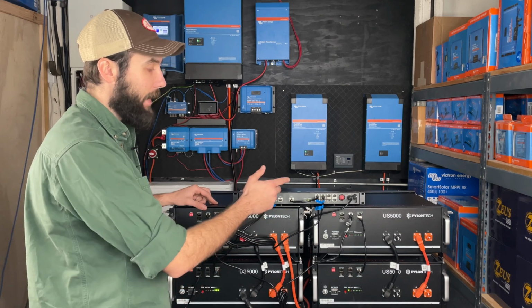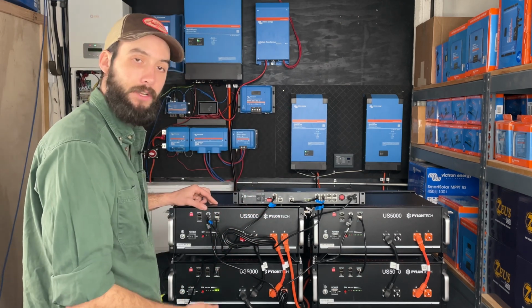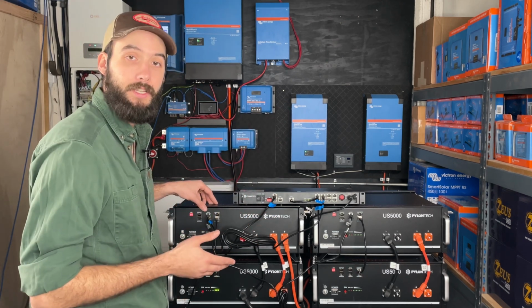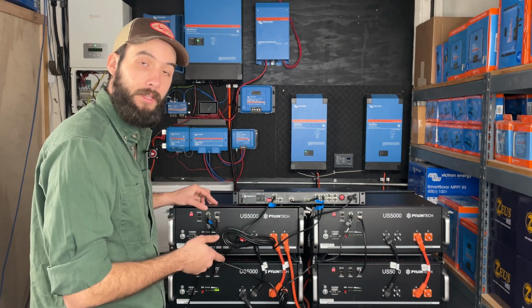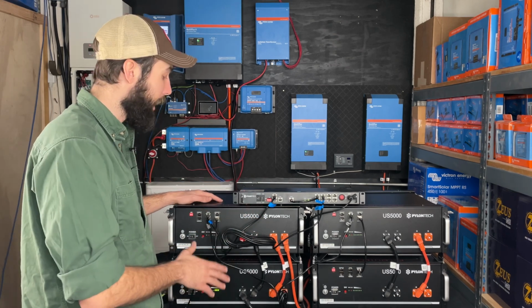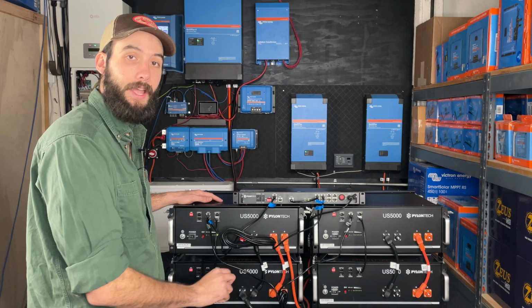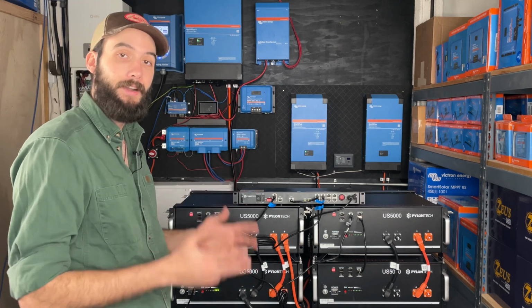So if we had a stack of 16 batteries, and for some reason, because it's an oversized system, I only had one set of end runs, that's fine. It will compensate for all the batteries in the middle of the stack to make sure they actually come up and down at the same time.